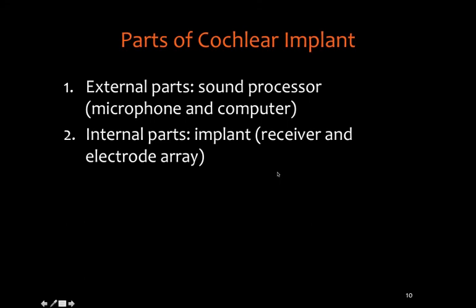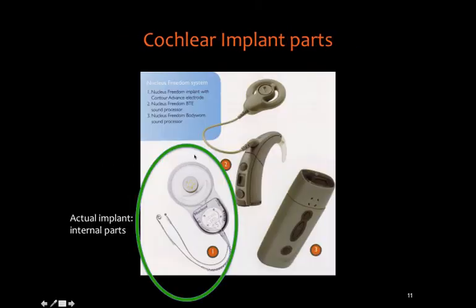When we look at the parts of the cochlear implant, it is divided basically into the external parts, the sound processor, which has the microphone and the computer, and then the internal parts, which has the implanted parts, the receiver, and then the electrode array, which is inserted into the cochlea itself.